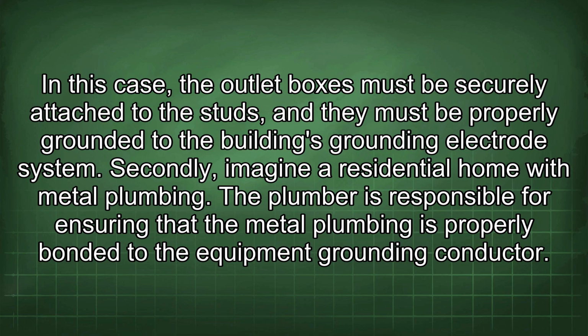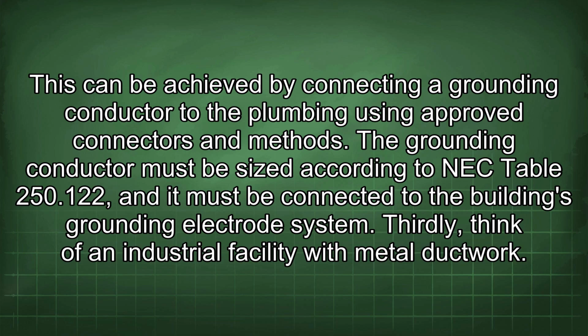Secondly, imagine a residential home with metal plumbing. The plumber is responsible for ensuring that the metal plumbing is properly bonded to the equipment grounding conductor. This can be achieved by connecting a grounding conductor to the plumbing using approved connectors and methods. The grounding conductor must be sized according to NEC Table 250.122, and it must be connected to the building's grounding electrode system.